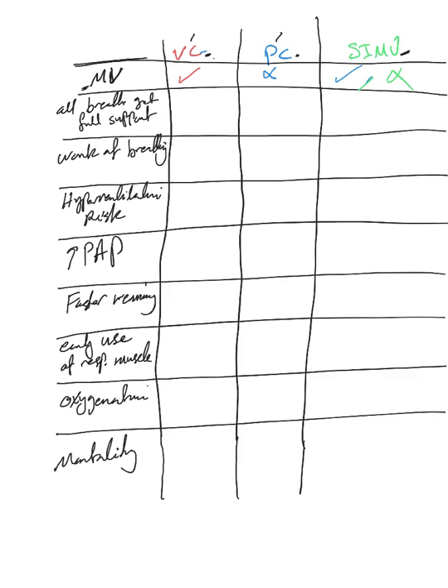All breaths get full support in volume control and pressure control. In SIMV, only the backup rate breaths get full support — any extra breaths above the backup rate receive only partial support or zero support, depending on your settings. This means work of breathing is less in volume control and pressure control, and more in SIMV.